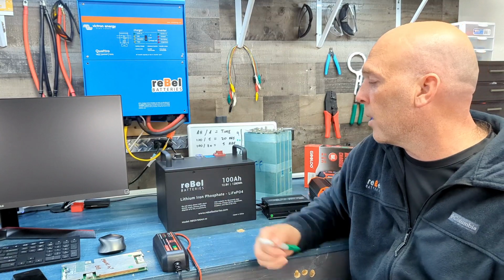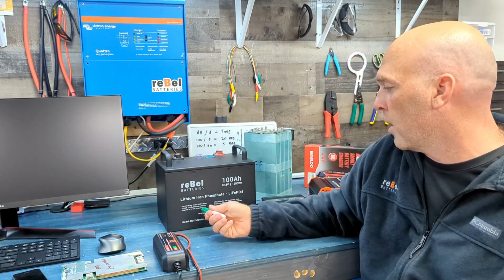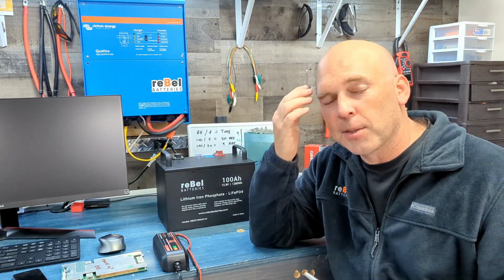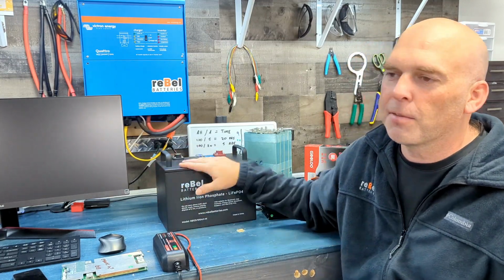So my suggestion, and what we put on the front, is to store at 75% - actually that's not on this one, it's on our plastic case battery. Store at 75%, charge once every 6 months. That's just a loose guide. If you leave it at 75%, you could leave it for a year and a half, since they self-discharge at 1 to 2% per month.